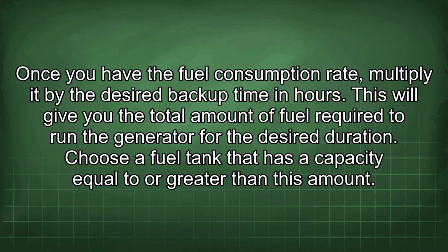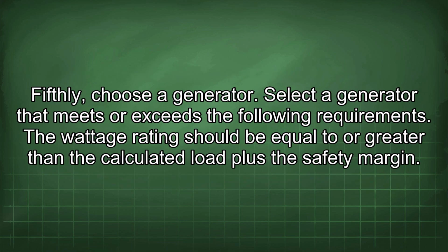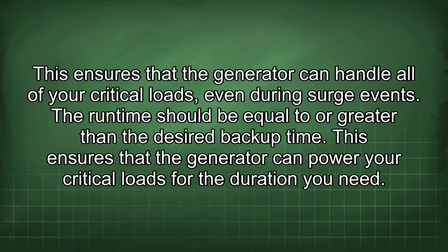Once you have the fuel consumption rate, multiply it by the desired backup time in hours. This will give you the total amount of fuel required to run the generator for the desired duration. Choose a fuel tank that has a capacity equal to or greater than this amount. Fifthly, choose a generator. Select a generator that meets or exceeds the following requirements. The wattage rating should be equal to or greater than the calculated load plus the safety margin. This ensures that the generator can handle all of your critical loads, even during surge events.